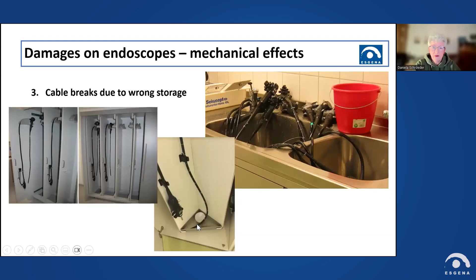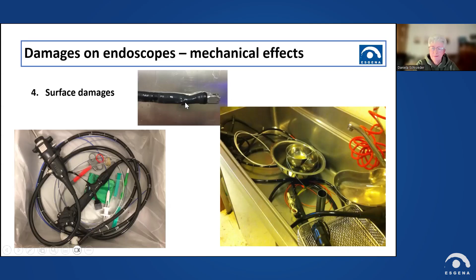Everything together for pre-cleaning in the sink, even the sharp materials. It's not only that our endoscope has a higher risk, but also yourself as staff, as a worker or an employee in reprocessing. Everything is carried from the procedure room to the reprocessing, everything together, and then it's separated. But this is a high risk too. Even the valve has metal parts, which have some influence or some attraction on the material of our endoscope. And this can result in this kind of appearances.